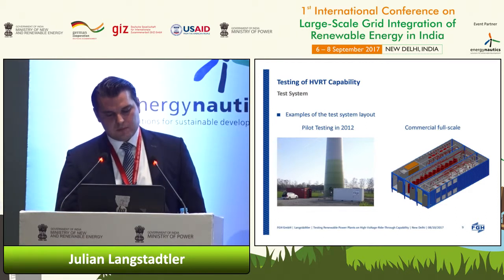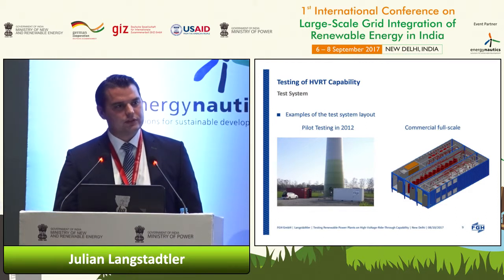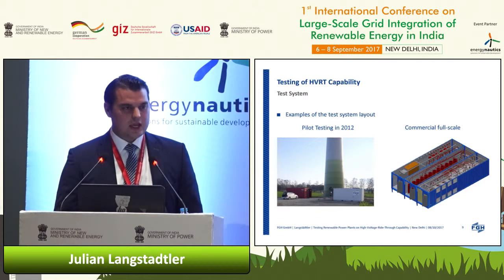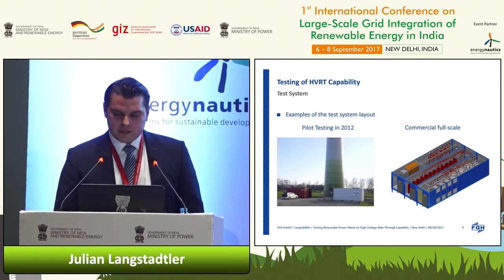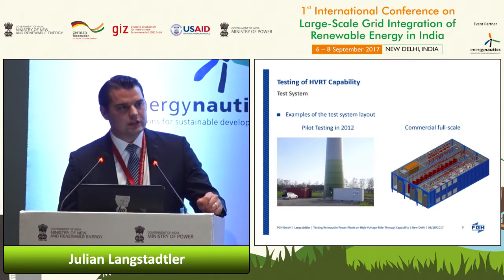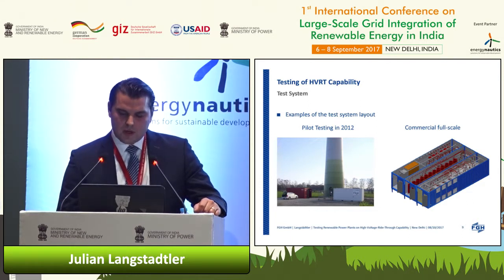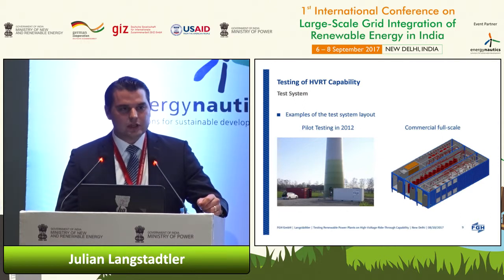The one that we built for pilot testing in 2012, which we did together with the wind turbine manufacturer Enercon in Germany, was a prototype rated only for 2 megawatts for LVRT, including the switchgear, whereas here there's the HVRT add-on system. Here you can see a commercial full-scale system, integrated in three 40-feet shipping containers, so it's quite a huge system. One container contains all the switchgear and the circuit breakers. The other contains all the inductances for the serial or short circuit inductances, and one container is full of capacitors and resistors.